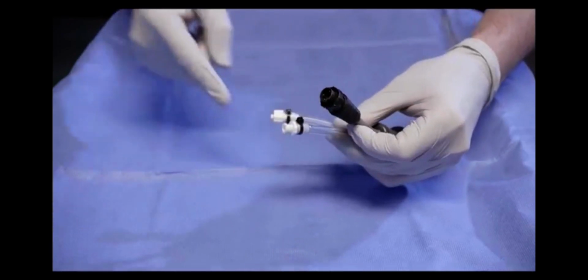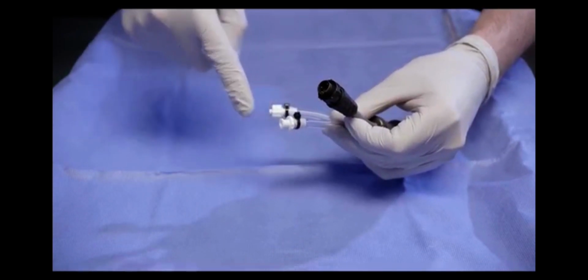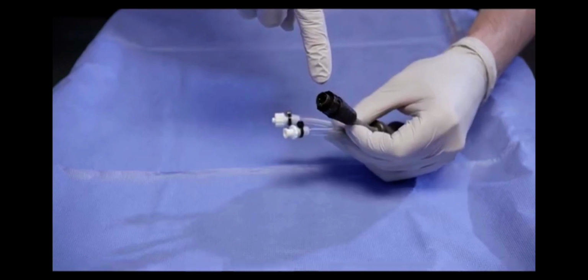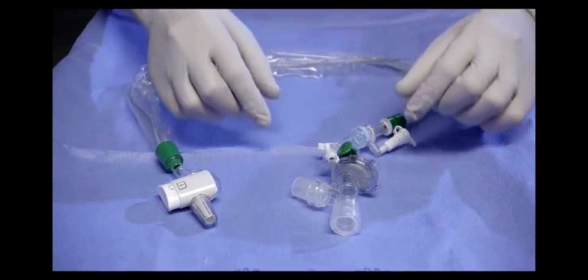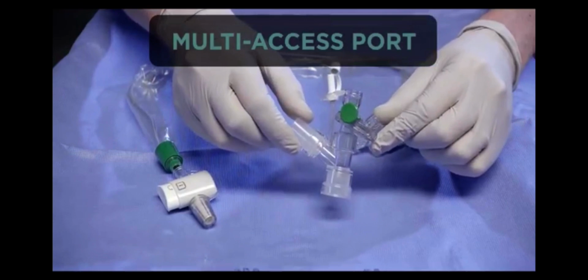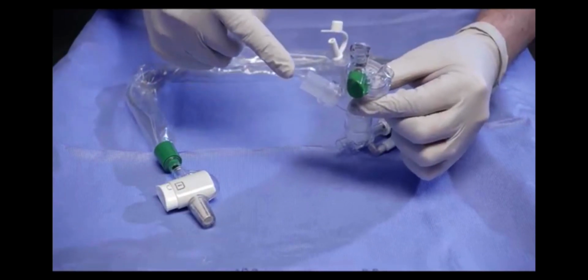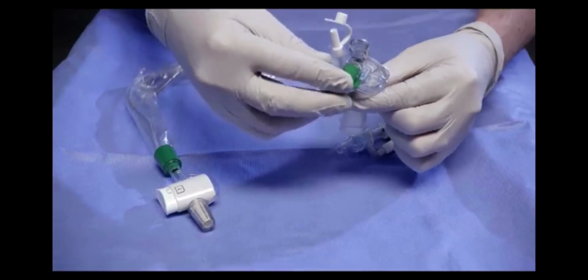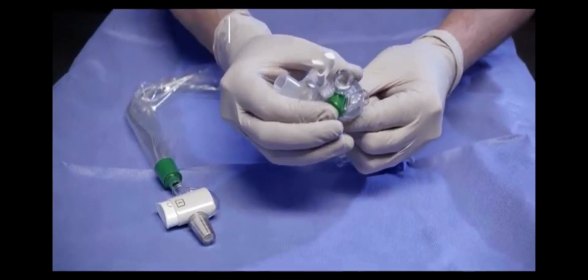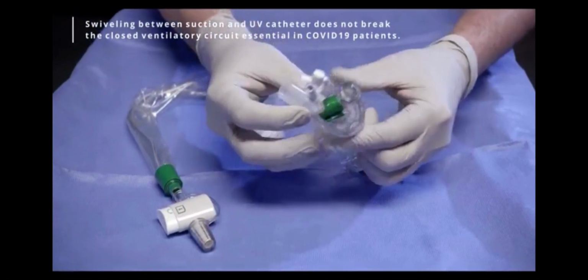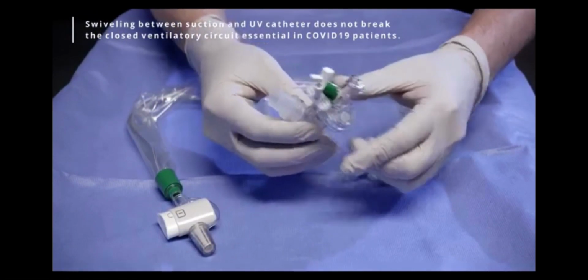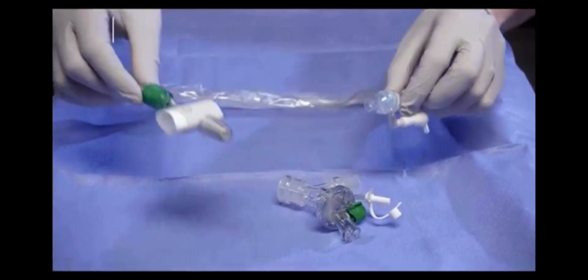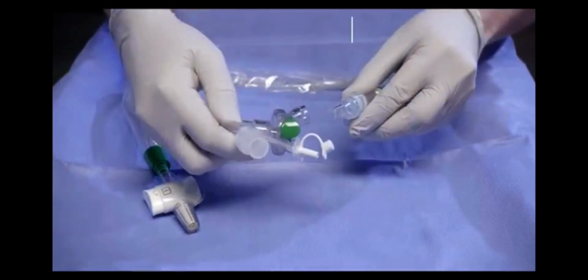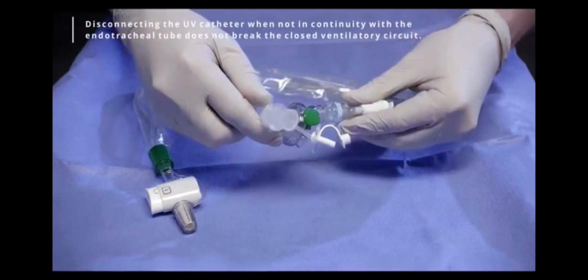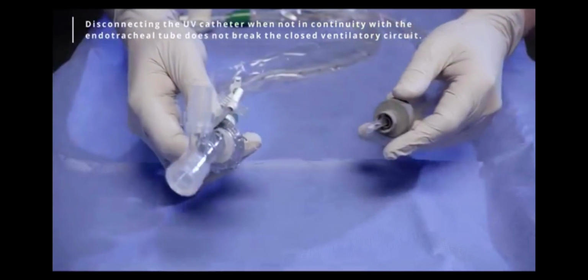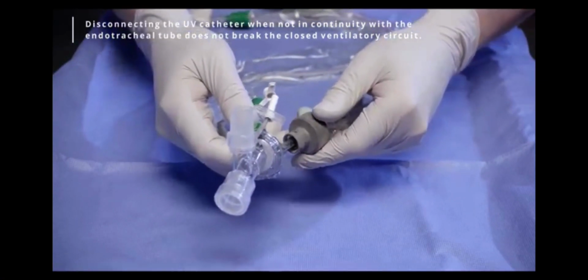And then at the distal end, we have the air connectors as well as the electrical connector, which get connected to the umbilical. Here's the three-way multi-port connector, which can be connected to the ventilator as well as a respiratory catheter, and then the UV light catheter, each of which has its own port, and a swivel mechanism that can be used to engage either the respiratory catheter or the UV light catheter as needed. Shown here is connection of the respiratory catheter as well as the UV light catheter to two of those ports.